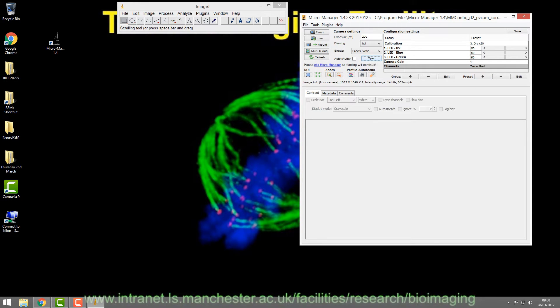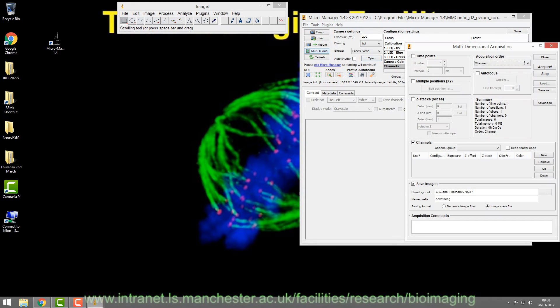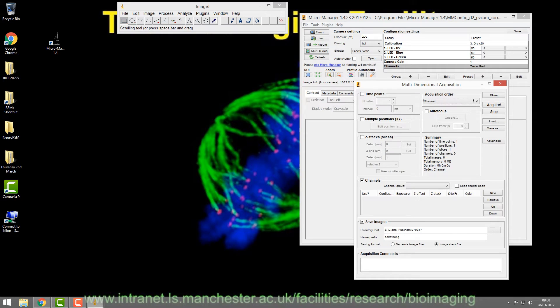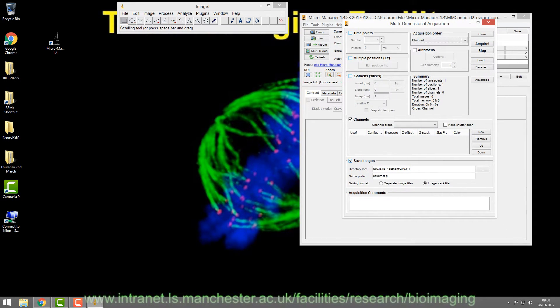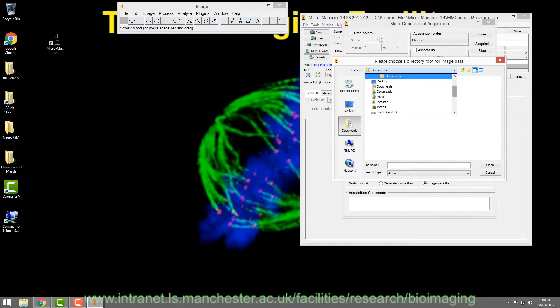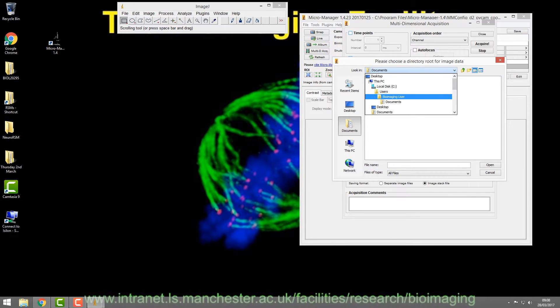When you're ready to start taking pictures, we're going to use Multi-Dimensional Acquisition. This allows you to control everything — you can do time lapse, multi-point, and Z-stacks, though we can't do Z-stacks because only the filter wheel is motorized; everything else is manual. What we can do is acquire channels and define where the images are automatically saved. If you log into Isilon at the beginning, you can save directly onto Isilon rather than transferring files one by one.